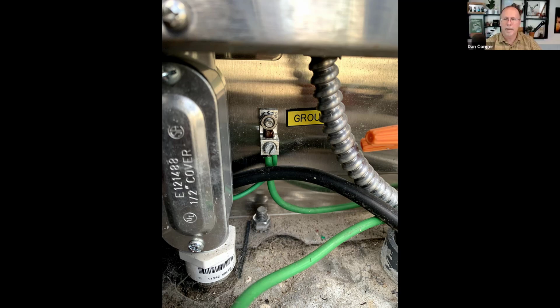Okay. So that's part of our wire spec, our ground spec: there's a minimum distance away from the controller and away from the wire path that this needs to be, because when a strike dissipates the energy out to the ground point, there's that sphere of influence, and we don't want that energy coming right back to the controller. So generally it's the length of the rod away from the device you're trying to protect. 8-foot rod, 8 feet away from the device; 10-foot rod, 10 feet away.